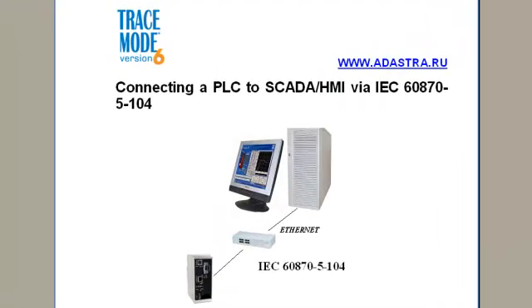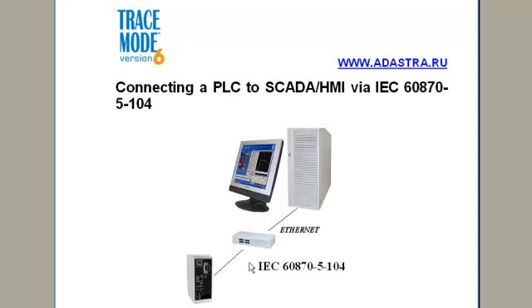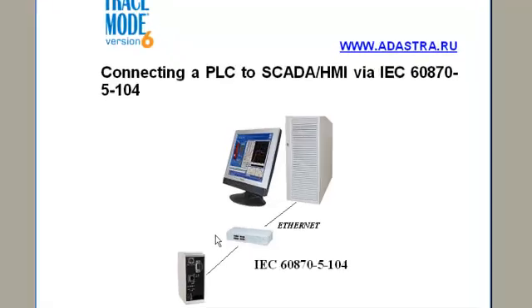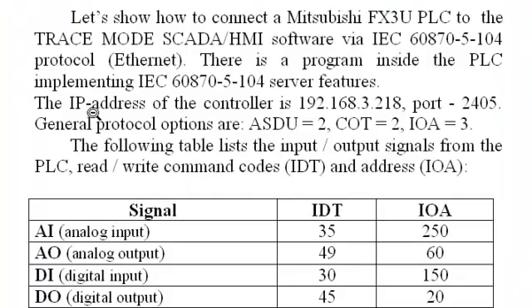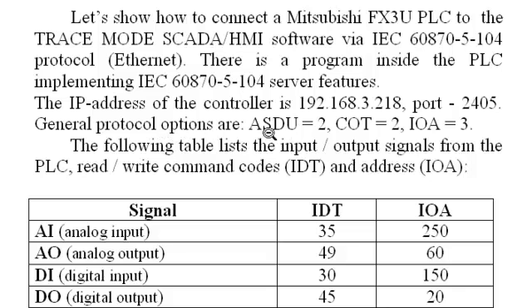Let's show how to connect a Mitsubishi FX3U PLC to the TRACE MODE SCADA HMI software via IEC 60870-5-104 telecontrol protocol (Ethernet). There is a program inside the PLC implementing IEC 104 server features. The IP address of the controller is 192.168.3.218, port 2405.